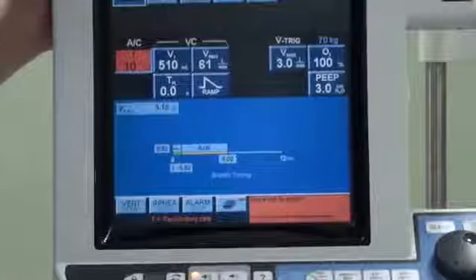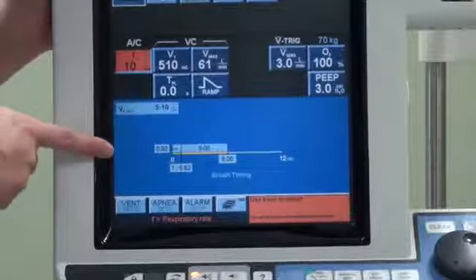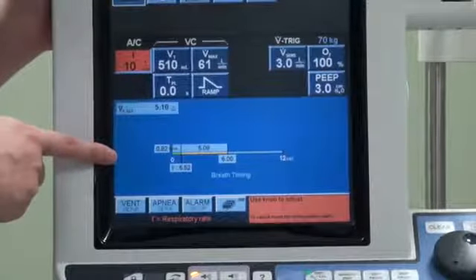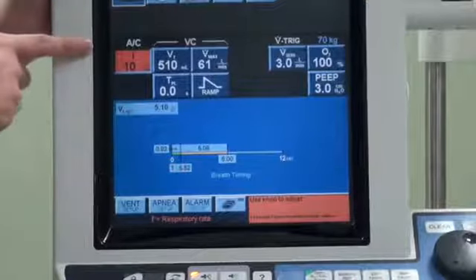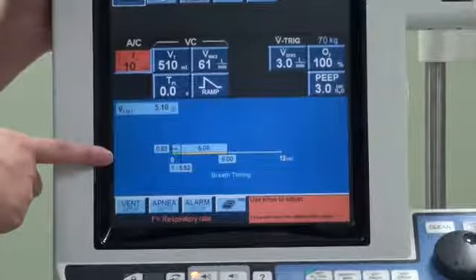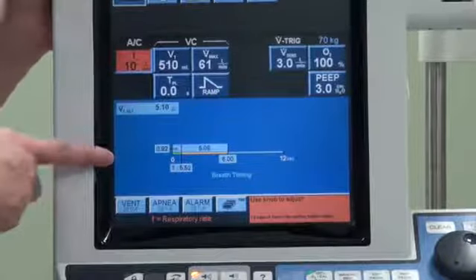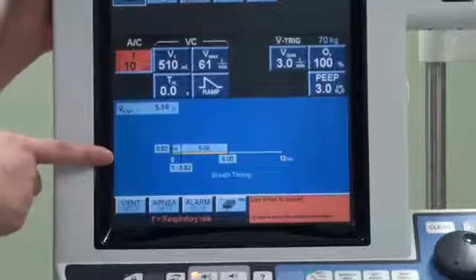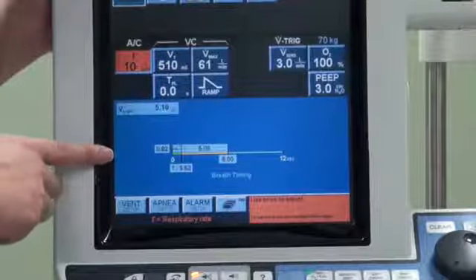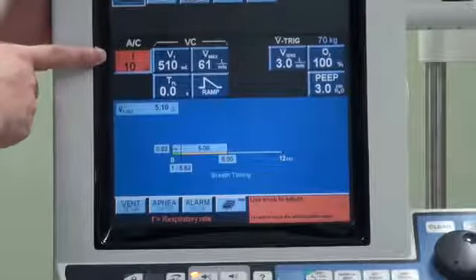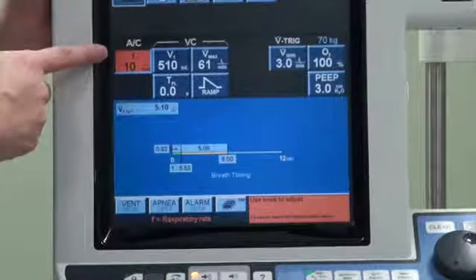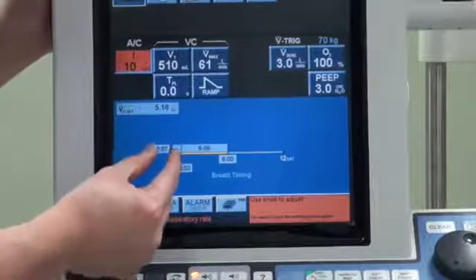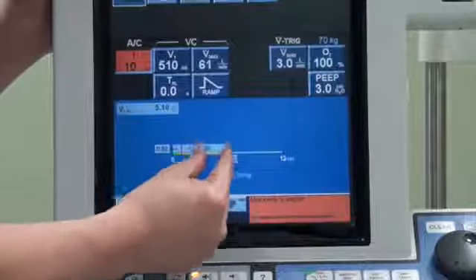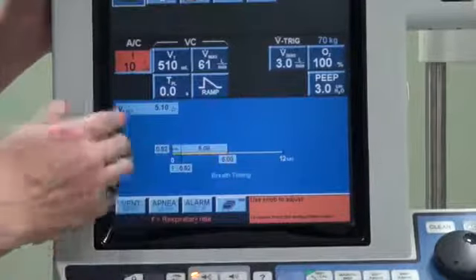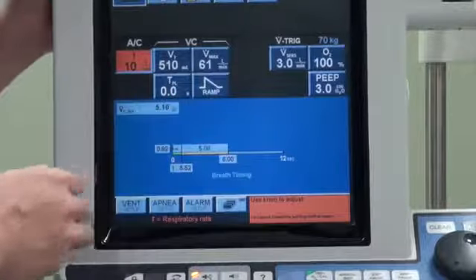You also notice that there is a second screen that will change depending on the settings that you're above. This gives us a representation of the inspiratory and expiratory time. So when you are setting a frequency of 10, your respiratory cycle will be about 6 seconds. And the machine will tell you how much time is spent on inspiration versus how much time is spent on expiration. And that will give you the inspiration to expiration ratio.